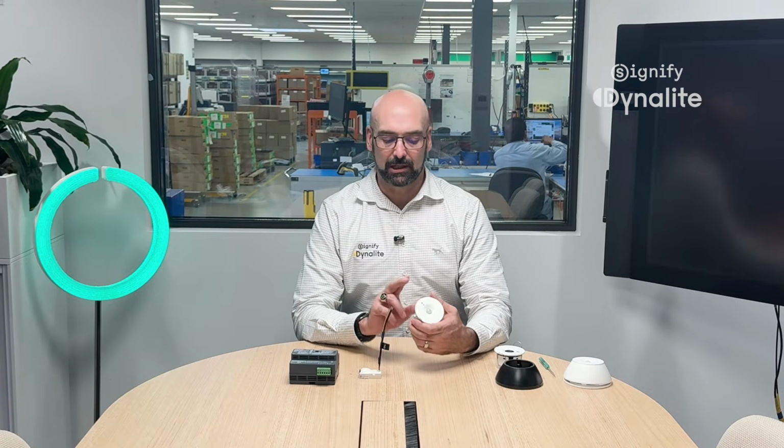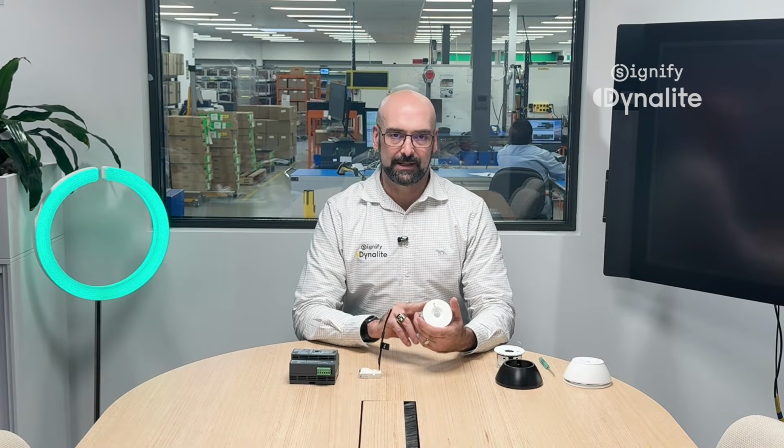So with a system that is without any drivers due to the power restrictions, being able to have 40 sensors on a single network is a huge achievement. Yes, there are the addressing limitations, but it is more of the system's ability to deliver power. This has been achieved because of the sensor's extremely low power consumption.